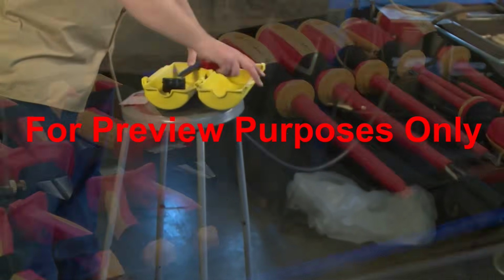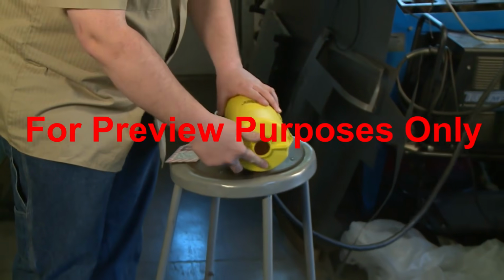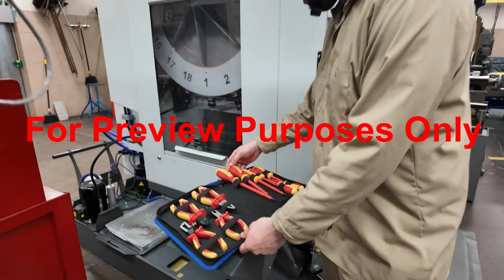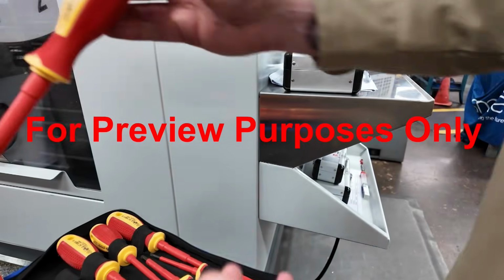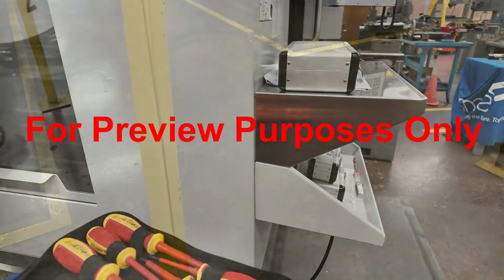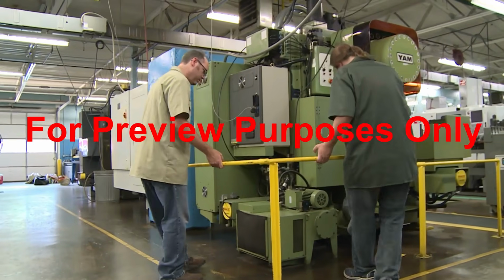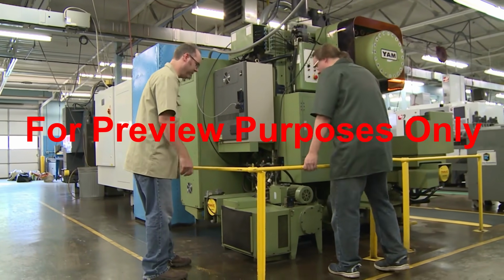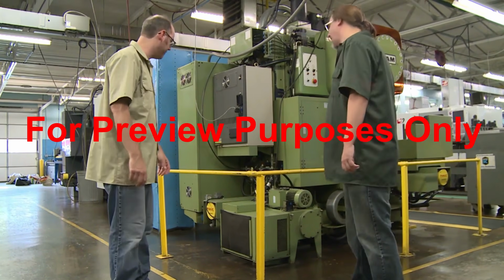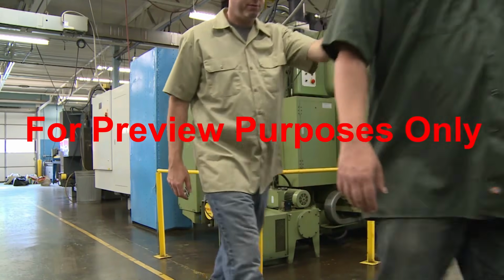It's also important to use the right tools and protective equipment when you're working around electrical hazards. Any tools that you work with within a restricted approach boundary area should be insulated and need to be rated for the voltages they are being used with. The NFPA 70E standard also lists physical or mechanical barriers that can be used as a protective measure when you're working around exposed energized electrical conductors that operate at 50 volts or more to prevent any accidental contact.